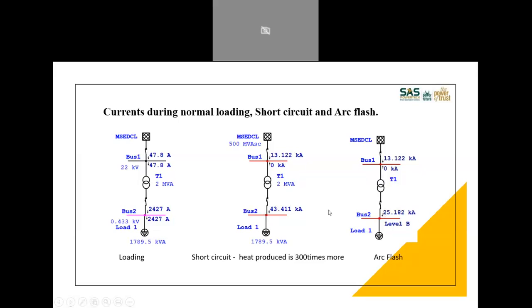Now let us come to the third figure. In the same scenario, instead of a bolted fault, where bolted fault is a technical term which actually means two conductors physically get connected to each other, we have an arc fault. As we saw in the previous discussion, it is actually not a physical connection, but there is an arc in between.